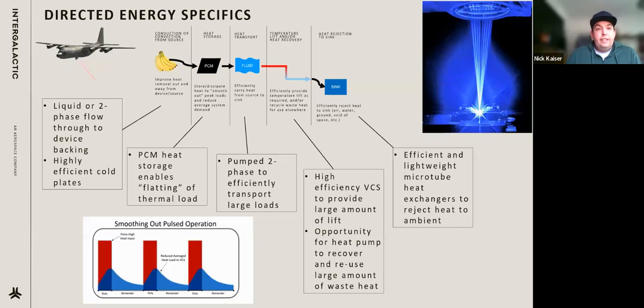Now getting into heat transport—something that can really help a lot, and something we're putting a lot of time into as a company—traditionally heat transport is air or a single phase coolant. Switching that over to a pumped two-phase solution can reduce the size, weight, and power draw of the system by a lot. We're talking orders of magnitude, and that's key because we're carrying hundreds of kilowatts, potentially up into the megawatt range in the not too distant future. Doing that with a traditional liquid system, you're talking hundreds of gallons per minute, high pressure drops, lots of power—you can literally divide that by ten if you convert to pumped two-phase. So that's a huge potential option there.